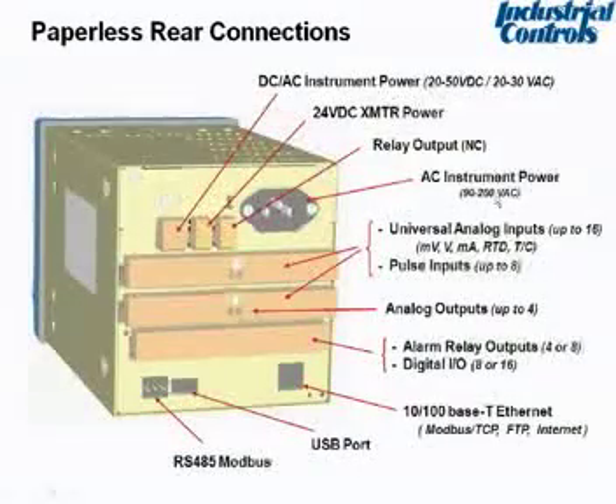115 volts AC is most typical, but there is also DC and AC instrument power. You can get a 24-volt DC onboard power supply to power those flow transmitters that we talked about, steam meters and gas meters. And then, depending on the size and the capability, you've got a number of cards for analog input channels, analog output channels, and a number of cards for relay outputs, digital in and digital out.